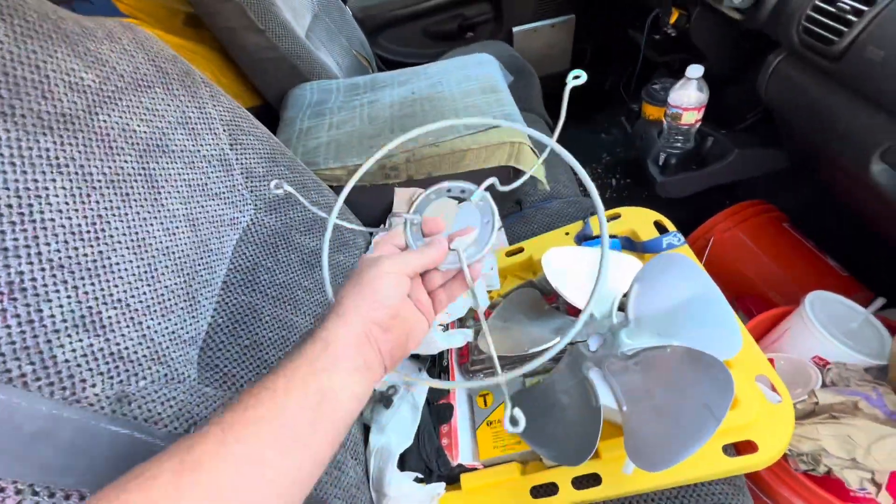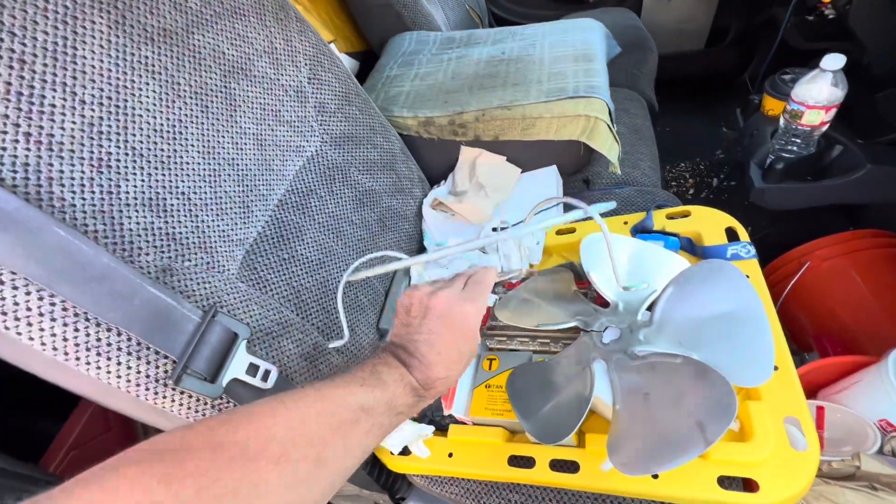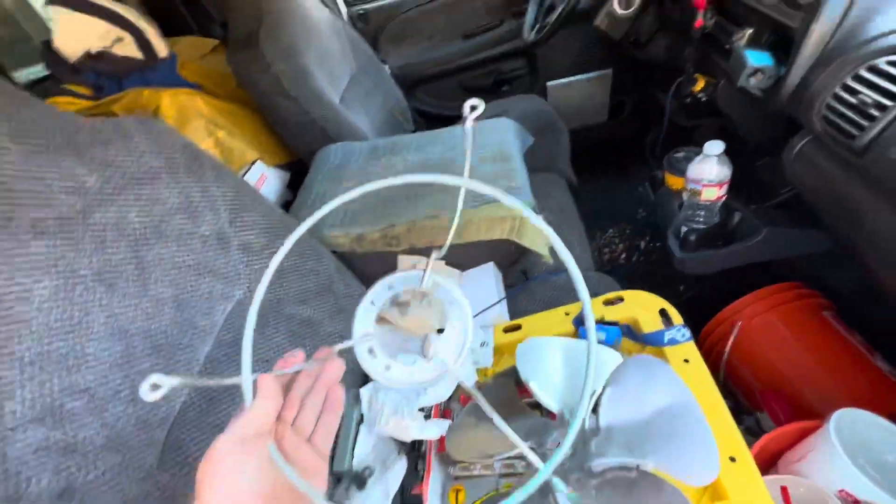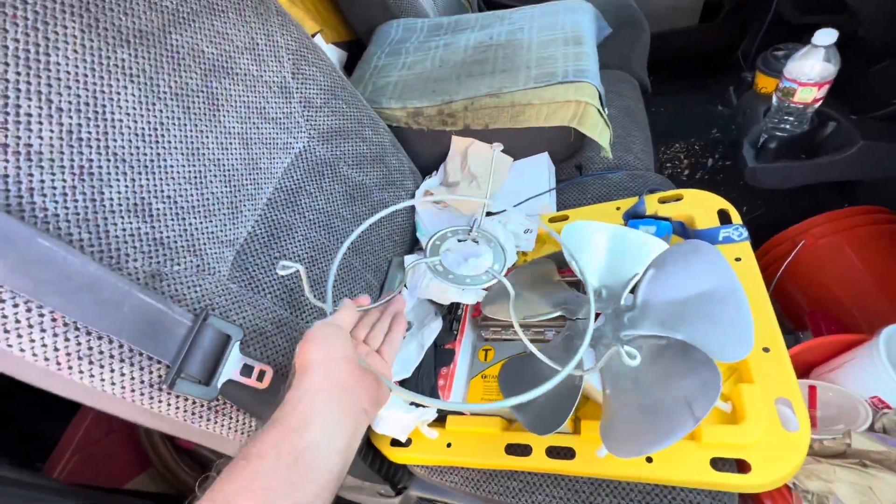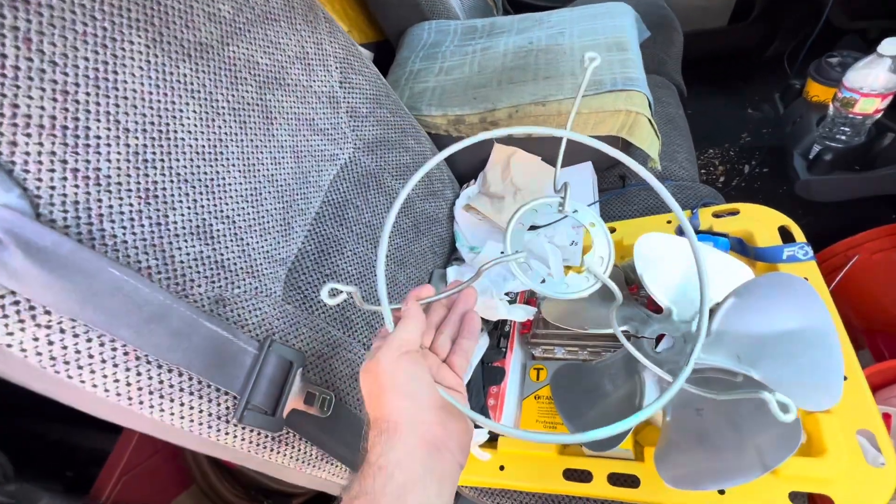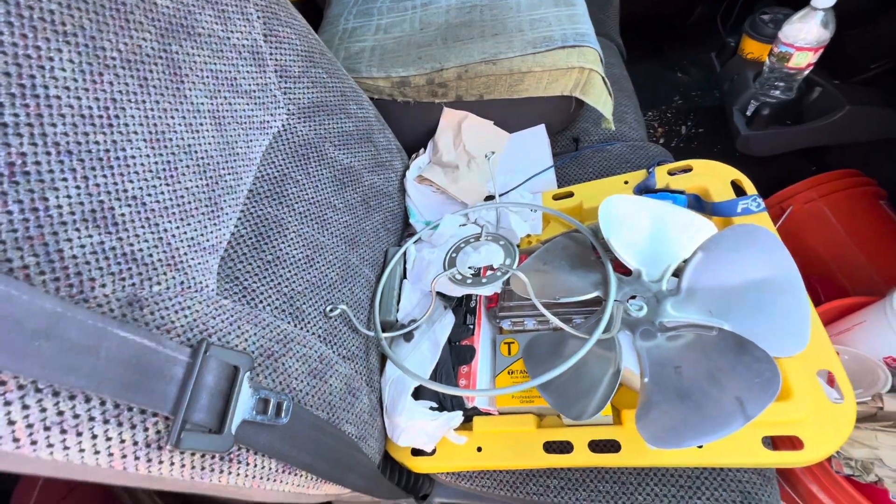Okay, I'm going to replace another one of these three-legged mounts. The other one broke. So check all your mounts guys, these three-legged things are probably breaking all over the place and you can't even tell they're broken without inspecting. They'll still be running for a while.